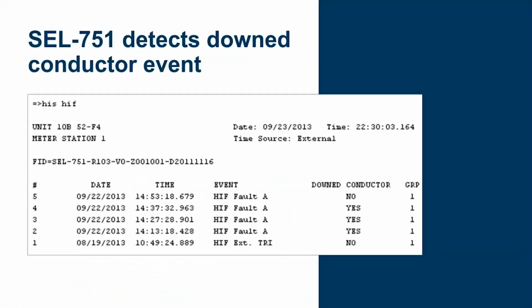This history command is from an actual 751 relay, and a 751 relay saw a high impedance fault. So again, you can see that you get the same information. And here the relay is detecting a high impedance fault on A phase, and you can see that it says it's an actual down conductor. So you get this information from the history command itself.